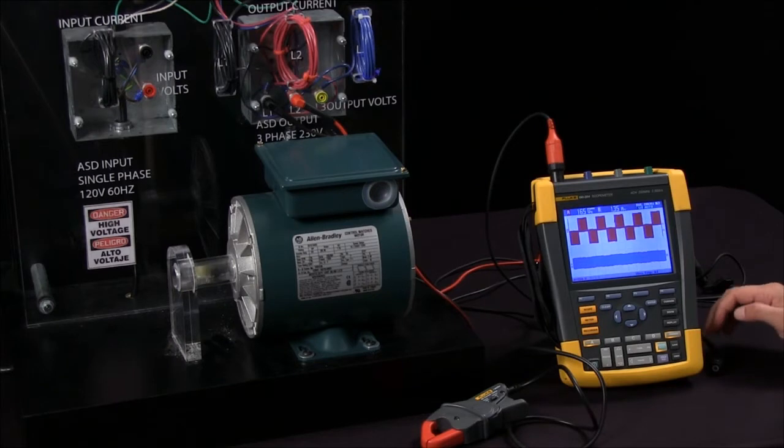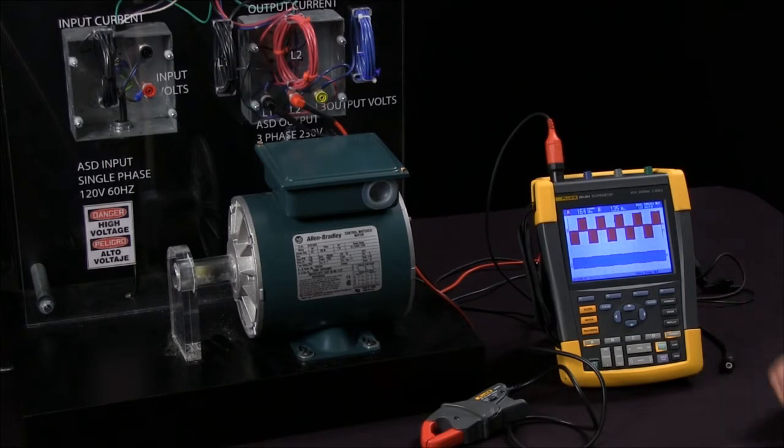As you can see on the screen currently I do have the output side of the voltage hooked up to the drive, so I am looking at a pulse width modulated signal. Now to utilize the scope to actually take a current measurement I am actually going to need to use an S style Fluke series clamp meter.